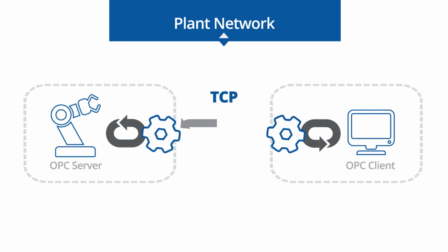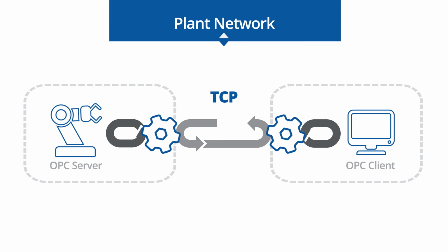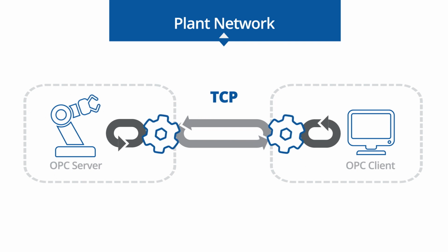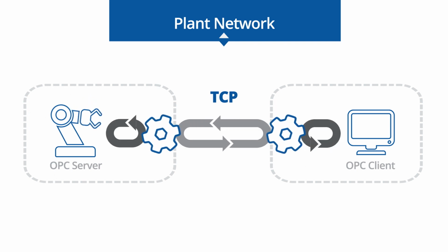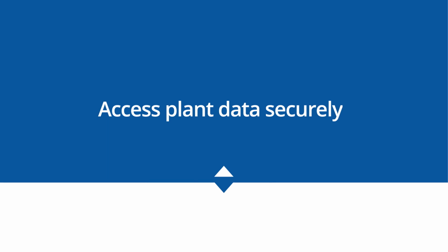It keeps all OPC communication local to the server and client machines, and then mirrors the data across the network. When there's a problem, the clients can keep working with the last known values from the data hub on their local system. When the network comes back up, both data hubs synchronize automatically. The clients never time out or freeze, waiting for an answer. The data hub fixes OPC networking within your plant. It also provides a secure way to access your data from outside the plant network.